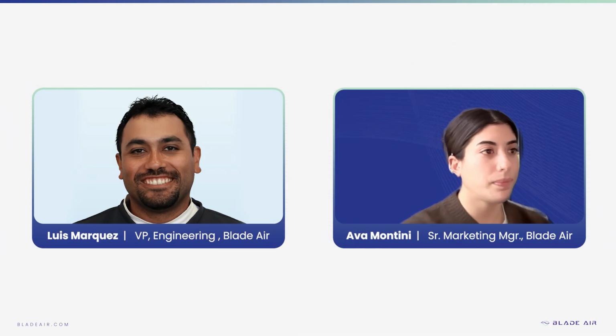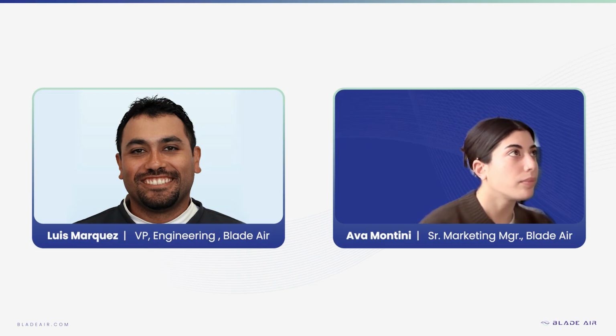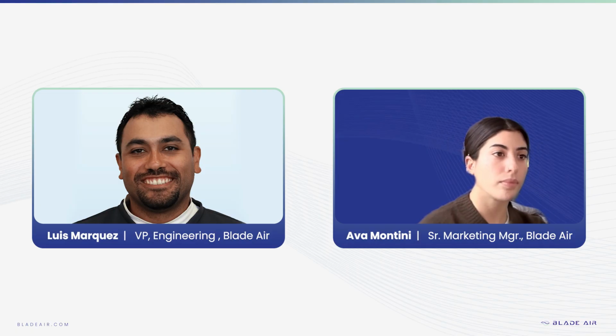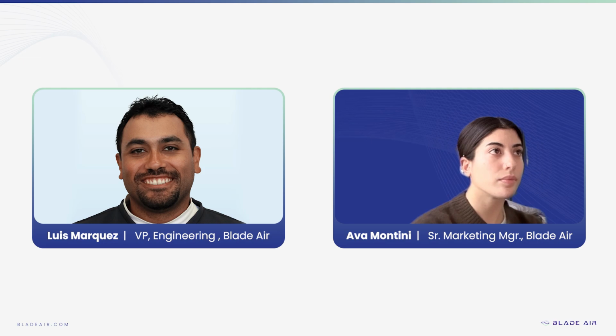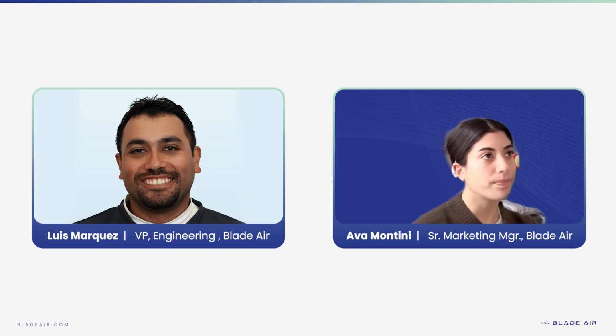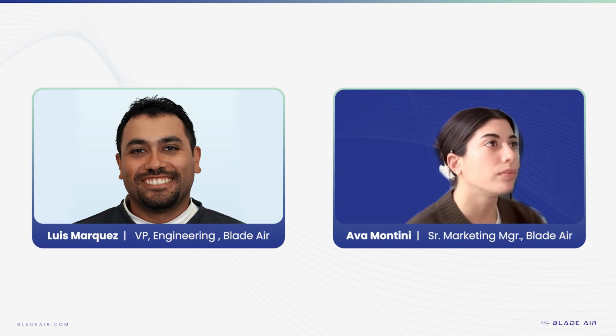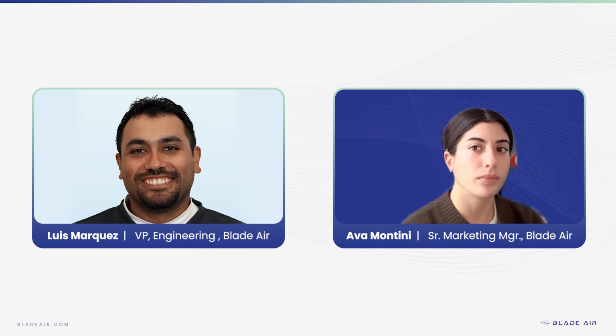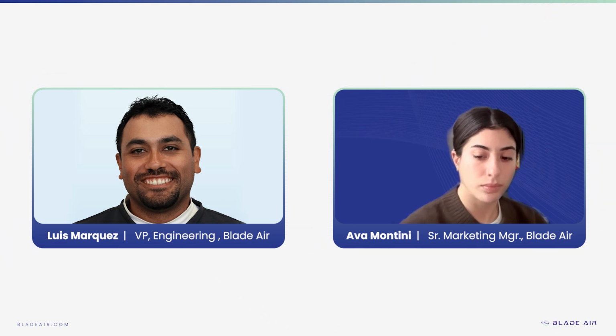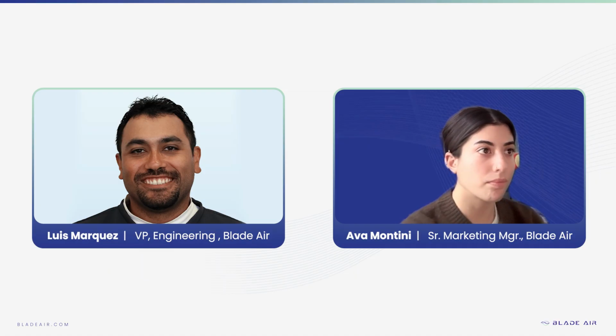Yeah, this is obviously a great point. Speaking from my company and our expertise, this is really how we function and consult for schools and many large commercial clients, and we've seen a lot of success implementing this. But it's about the education on how and why it happens. A lot of the industry is starting to catch on to what's called total cost of ownership of the filters, not just the initial pressure, but the entirety of the average pressure and when you actually need to swap out the filters. Because the longer you can extend that while maintaining your fan efficiency and your systems running smoothly, is where you get that additive effect and maximize efficiency. With the forefront of data centers searching for every percentage of efficiency, that's why we're here concentrating on this.